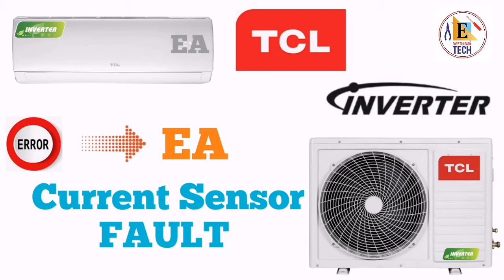In this, you have to check the voltage of 5 pin to 2 pin on power factor correction. If the voltage is not higher than 0.4 volt, then you have to replace the power factor correction. If the voltage is higher than 0.4 volt, then you have to replace the intelligent power module and your unit will be in working condition.